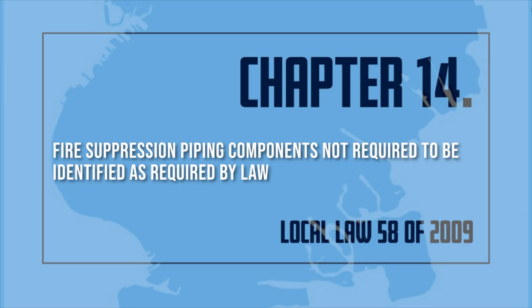Fire suppression piping components not required to be identified as required by Local Law 58/2009. Fire department hose valve bodies and handles, indicating control valve bodies, check valves, jockey pump control valves, trim, test, and drain valve handles. Standpipe, branch piping. The portion of the piping system connecting one or more hose valve stations. Sprinkler cross mains. The portion of the piping system supplying the branch lines either directly or through risers. Sprinkler feed mains. The portion of the piping system downstream of a sectional or floor control valve supplying cross mains. Sprinkler branch piping. The portion of the piping system to which the sprinkler heads or nozzles are directly connected. For more info, refer to New York City Building Code, Local Law 58/2009.